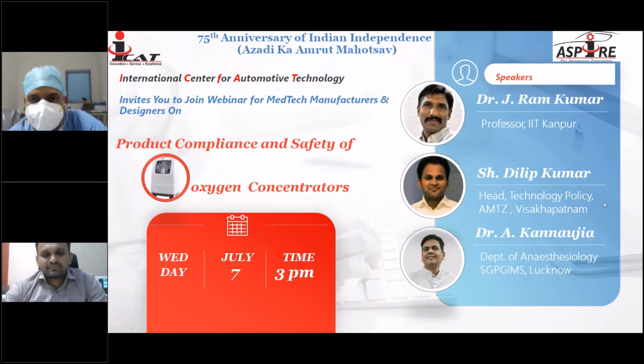That depends whether you want to test for particulate matter or for VOC. For VOC, it will be diluted if flows are higher, and it's temperature dependent also. So for VOC testing, the temperature should be the maximum allowable during clinical use, and the flows should be minimum. That is critical for VOC analysis. Regarding particulate matter, the higher the flows, the more particulate matter will be generated or thrown out.